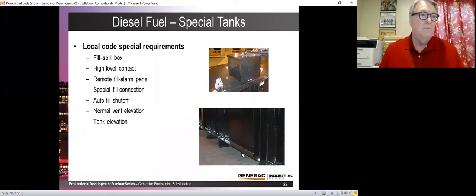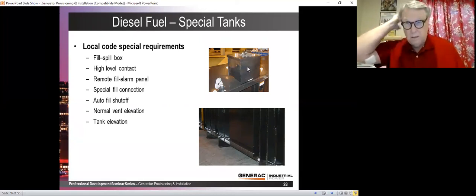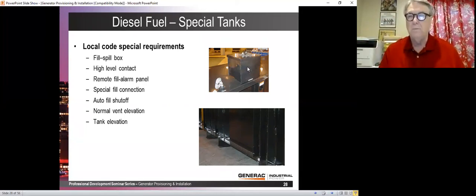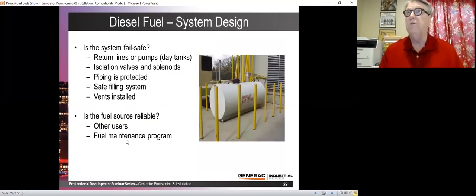Specials. We could spend forever talking about specials. This is a fuel spill box that if you are filling the generator with fuel and you spill, it goes into this box, and then you can lift a little lever and let that drain into the tank. This is quite unusual in the picture because that really messes up your mounting, where you're supposed to put the generator, right? So if you have something like that, you typically have to extend the generator or the tank out beyond where the generator mounts, and we can put fuel spill boxes. Not common, and you can see some of the other options there. I'm not going to go through all of them. There's lots of diesel fuel options.